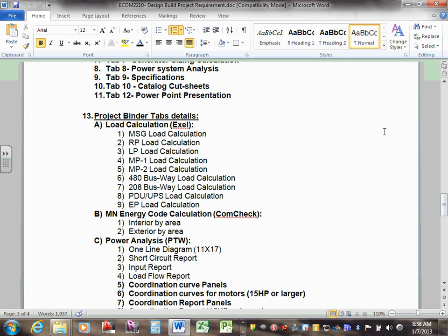Okay, now the project binder tab. The tab, guys, under load calculations, you have to pay attention to that one. Here's what I would like you guys to do when you do load calculation. What the heck is load calculation, Chad? I want you to do load calculation about these 9 items. And if you go to the load sheet that I showed you, it shows them as columns. So at the end of your load calc, I need to know what the size of the main switchgear, the receptacle panel, lighting panel, mechanical 1, mechanical 2 panels, 480 busway, 208 busway, PDU, UPS load, and emergency panel load. These have to be sized. That's the outcome of the load calculation. Cool. It's easier than you guys thought. Very much easier than you thought.